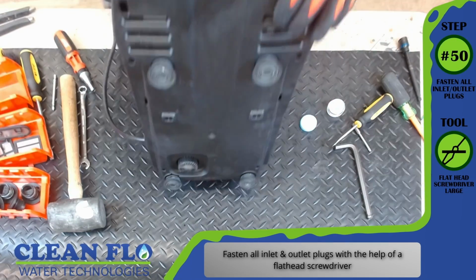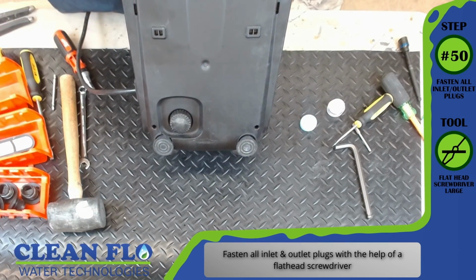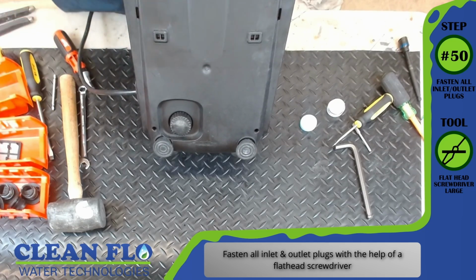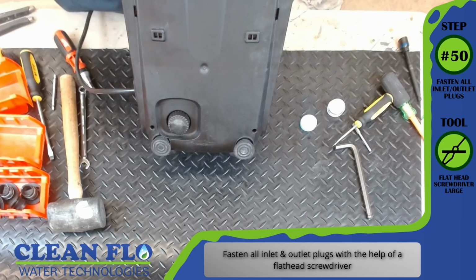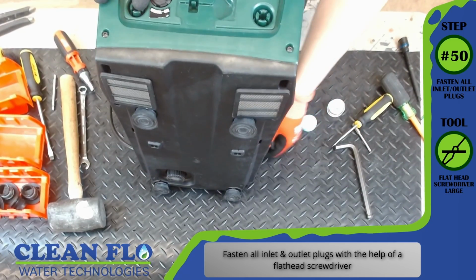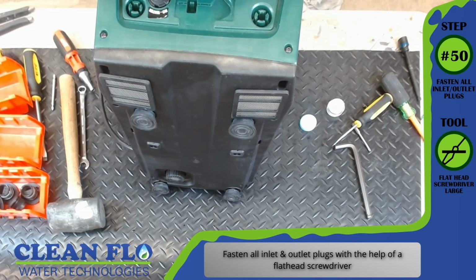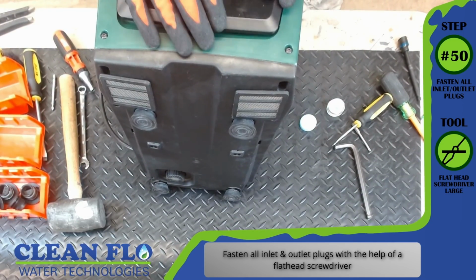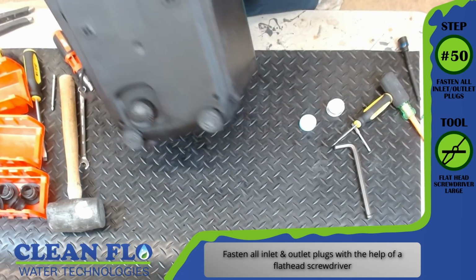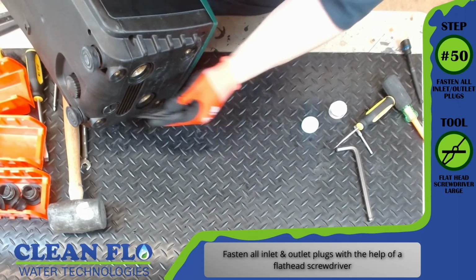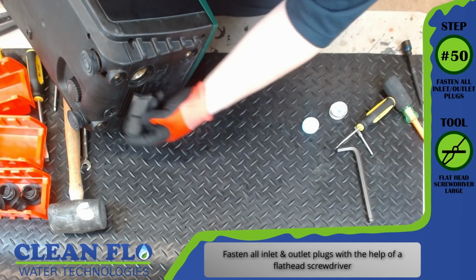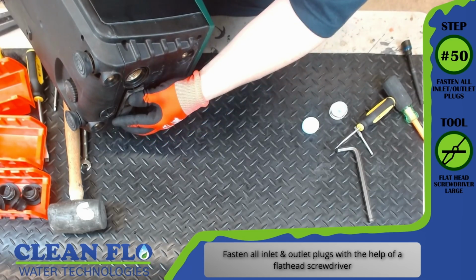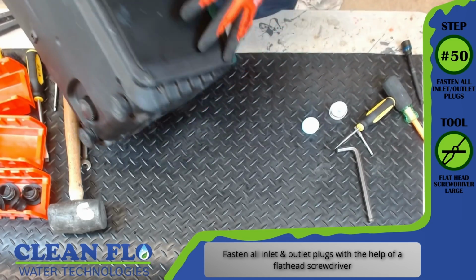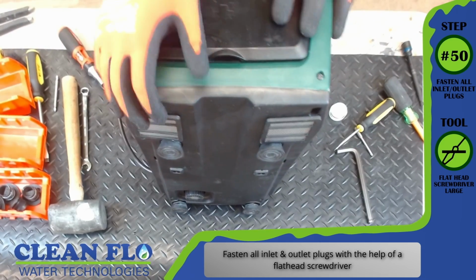Step number 50, fasten all inlet and outlet plugs. Tool, flathead screwdriver large. Fasten all inlet and outlet plugs with the help of a large flathead screwdriver. You can also clip on any of the vent covers that were removed during disassembly. There's 2 on the back and 1 on the bottom. These protect any debris from being sucked into the pump for cooling.